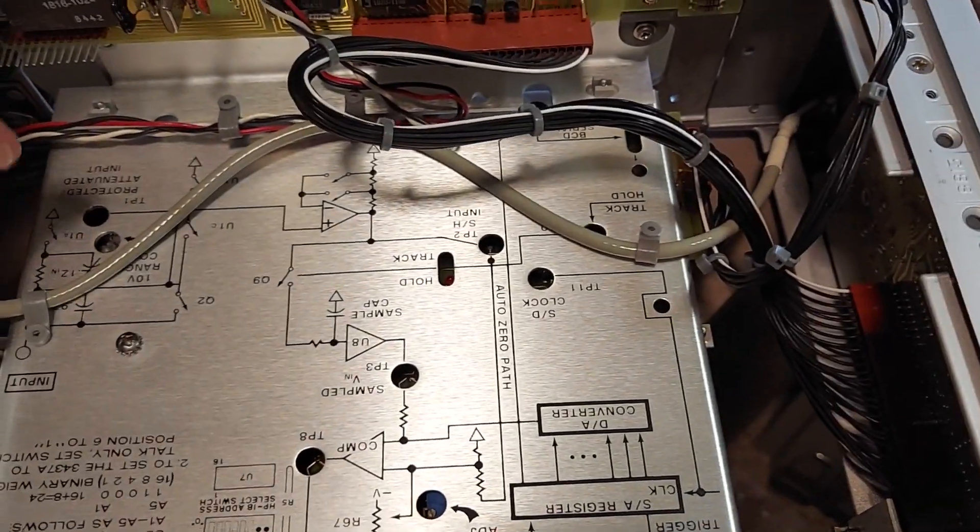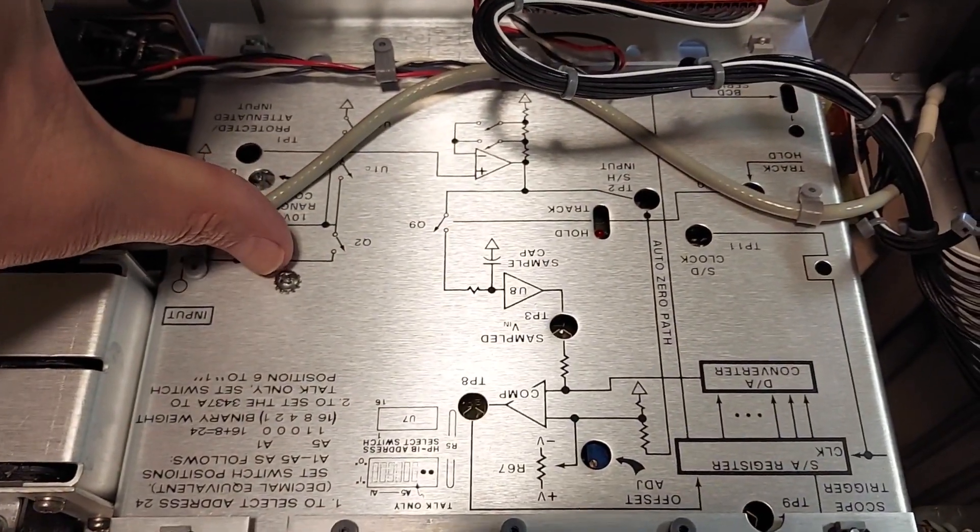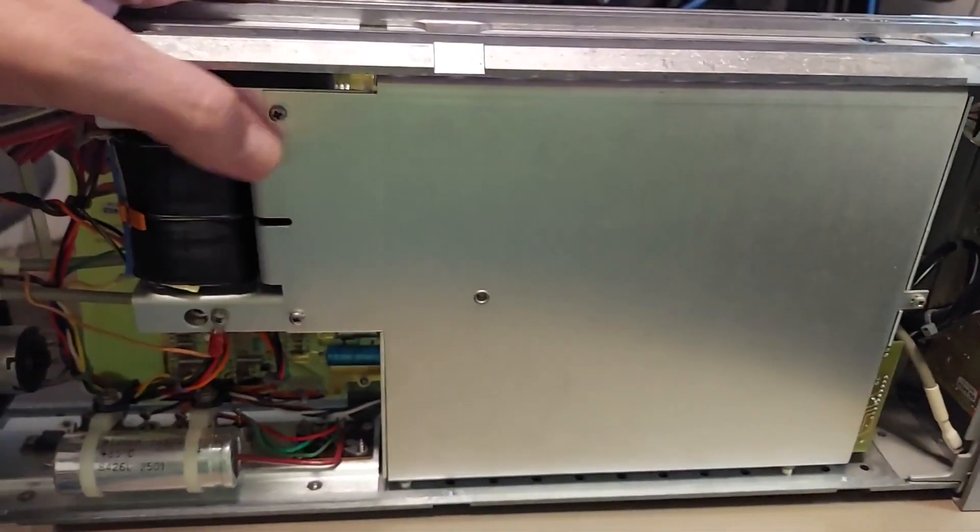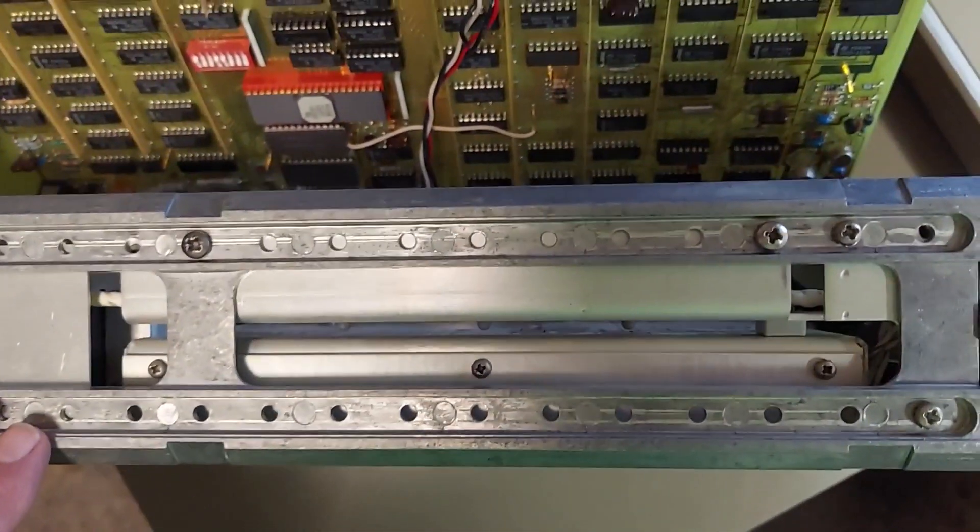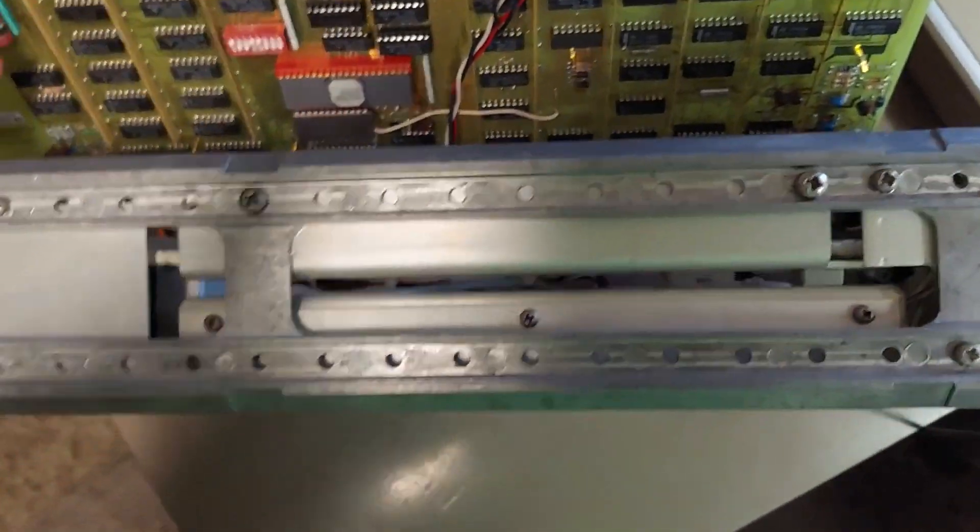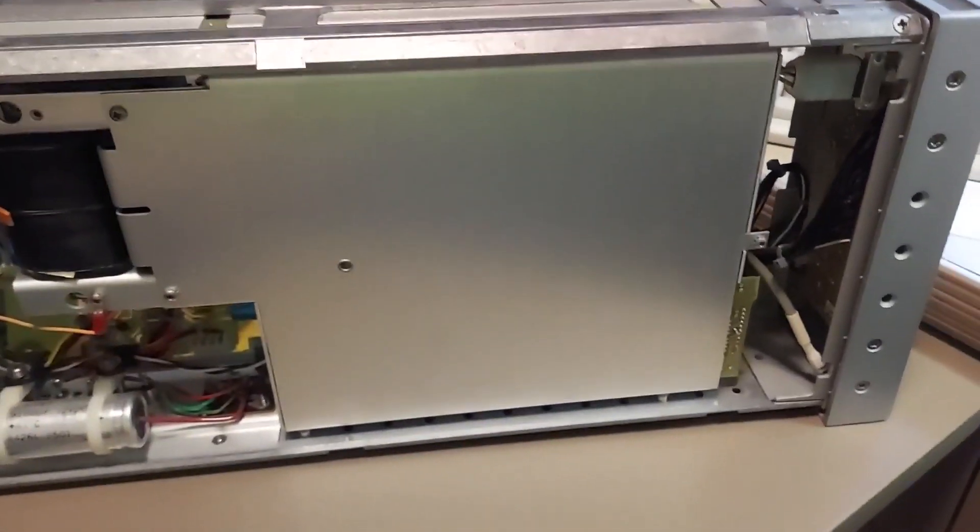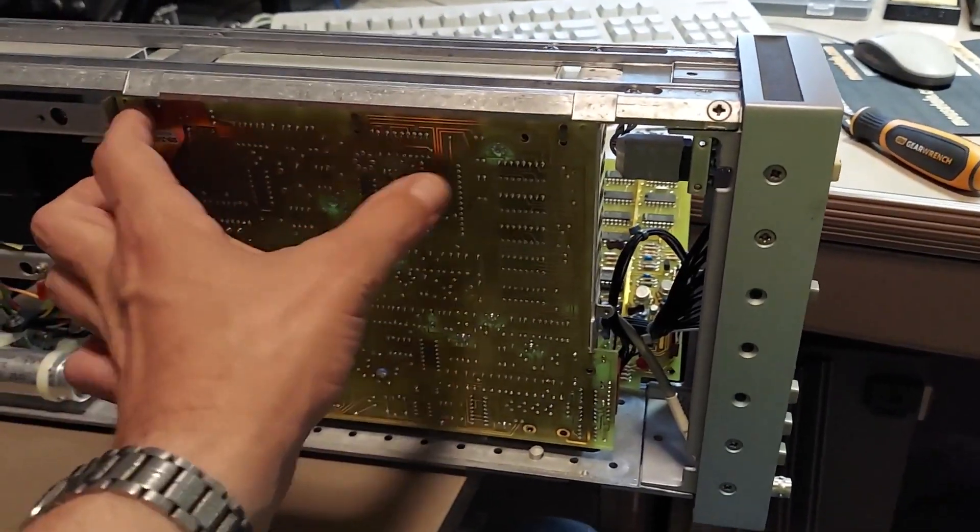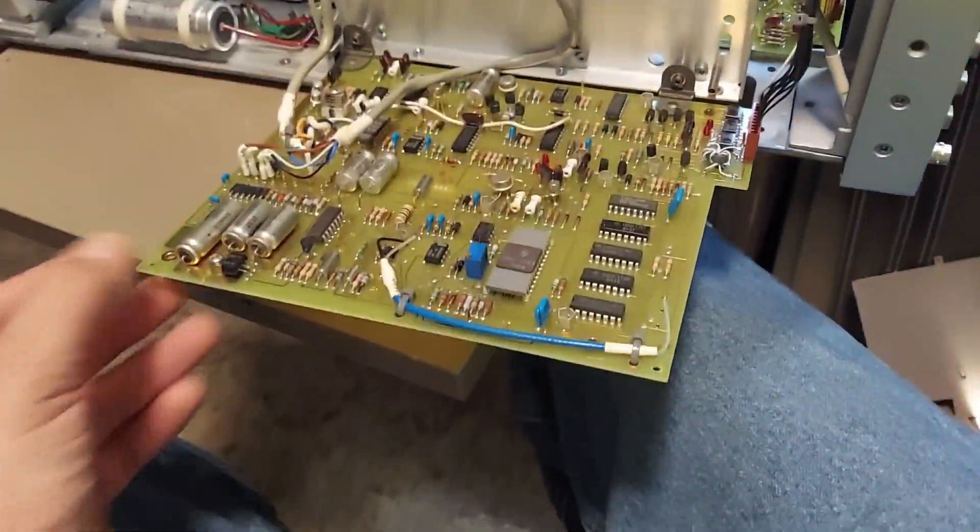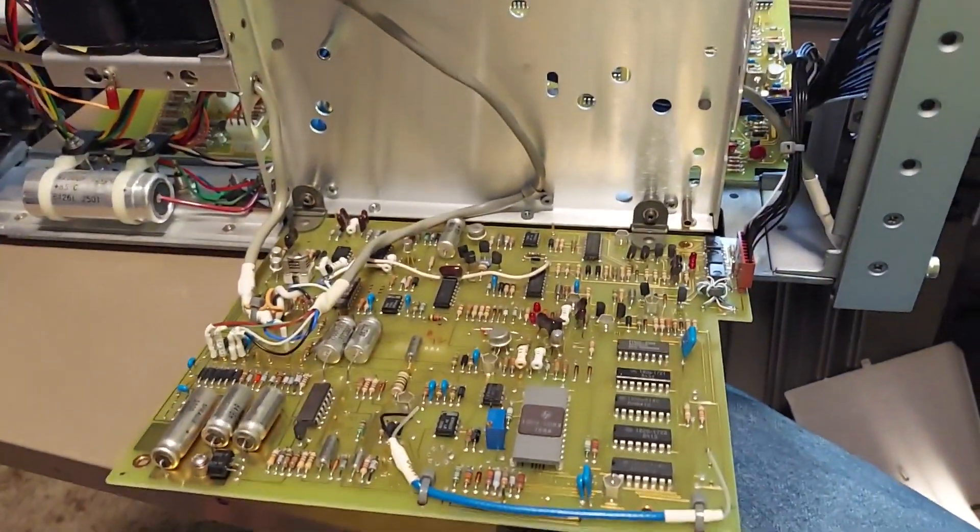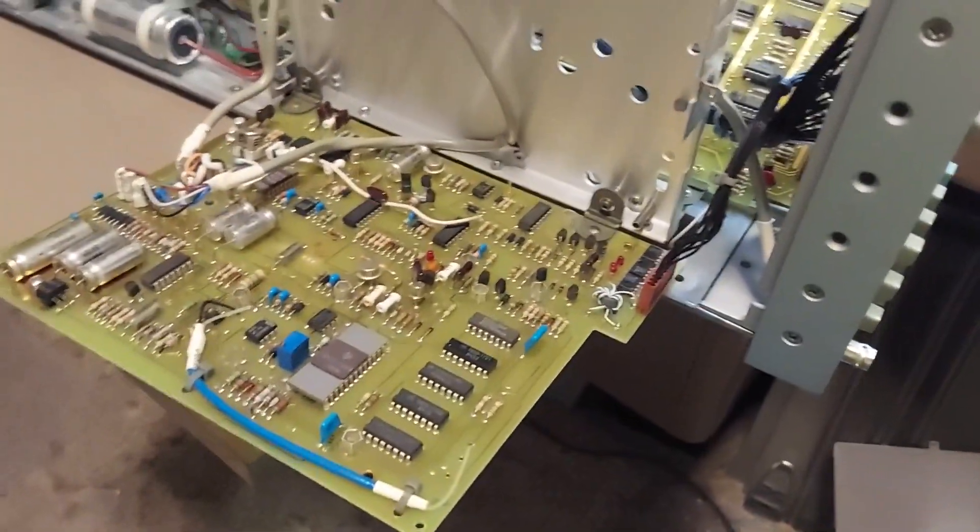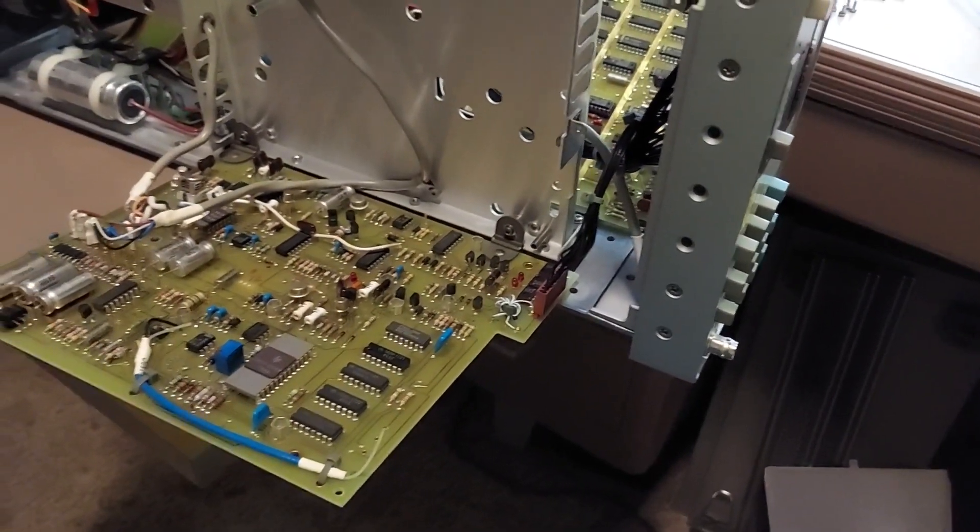Okay, now here is the old analog board. To get this out, we need to take that screw out. We need to take these screws out. And then on the sides, there are three screws, here, here, and here, on both sides that need to come out. And then this whole thing should just fold down. Okay, with the analog board, I've got three screws I had to take out. Now this board just folds right down. Just like the one on the other side, so it gives you a real convenient way to do your troubleshooting. So, without further ado, I will do a couple of small tests, and we'll see what there is to see.